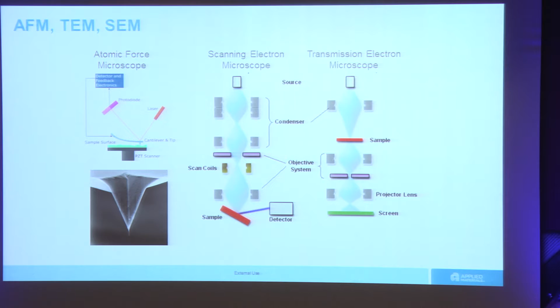The comparison between those systems: AFM is very, very accurate, and it's non-destructive, but it's very, very slow. Okay? TEM, transmission electron microscope, is very accurate, but it's destructive. Okay? And slow, of course. And the scanning electron microscope is not very accurate, but it's very fast compared to the other alternatives, and it's non-destructive. So now I'll tell you in a few words how we use scanning electron microscope to create 3D information from the device, to extract 3D information.